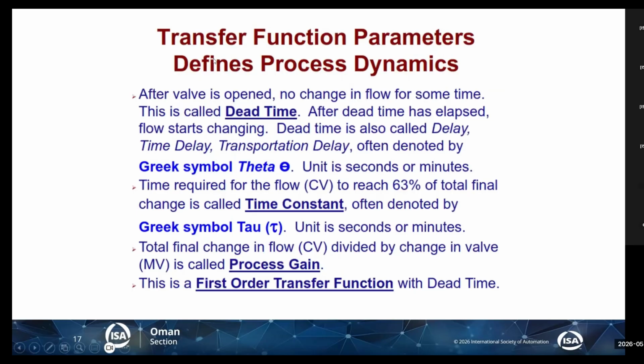And you can see here, as we mentioned before, the transfer function parameters. Our dead time is no change in flow for some time. So when you do a step change, when you open or close the valve, for maybe 5 seconds, 10 seconds, or in slow loops even minutes, you will not see any effect. You should not think the controller is not performing. This is a natural characteristic of the system, the loop. That time you can also call time delay.